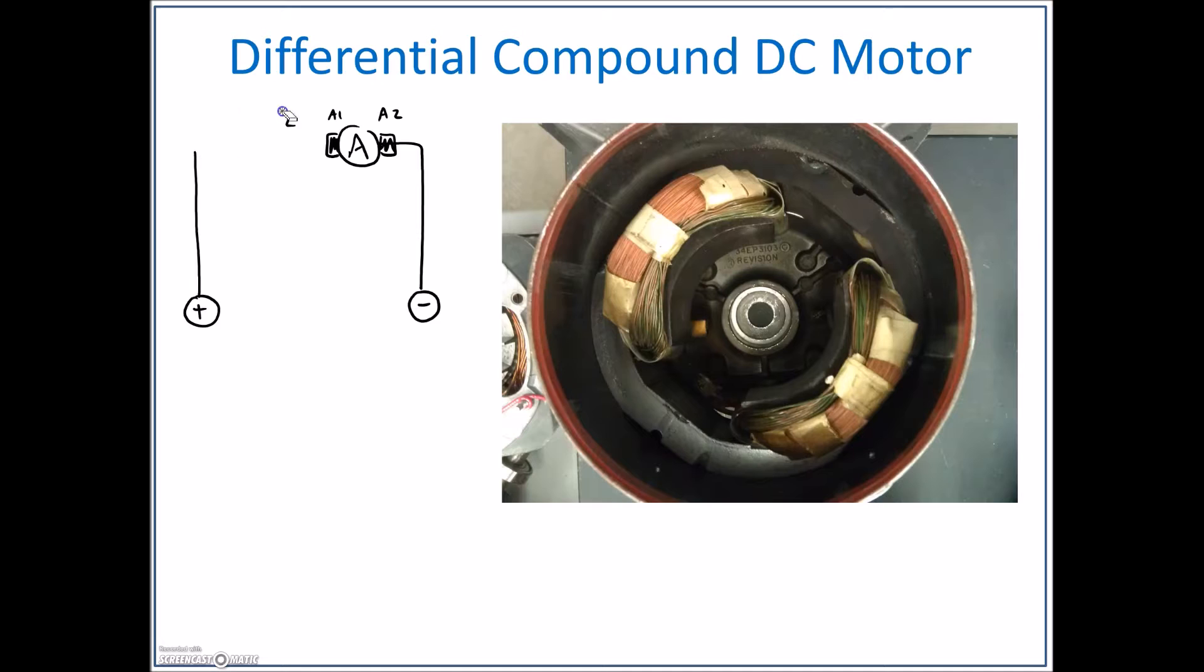Then we hooked it up as a shunt motor and saw which way it spun. If they were both spinning in the same direction, we knew that our magnetic polarity of both the series and the shunt were set up in the same direction. That was crucial because if we screw up the connections on the compound motor, some funky things happen.